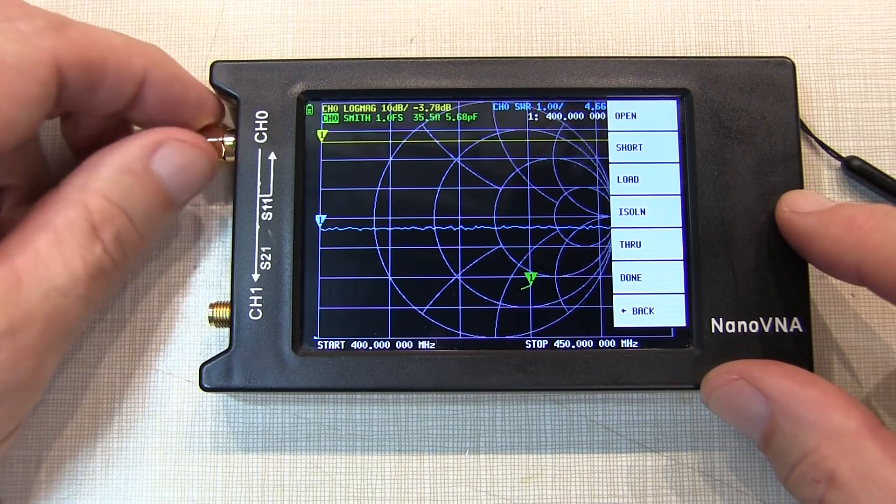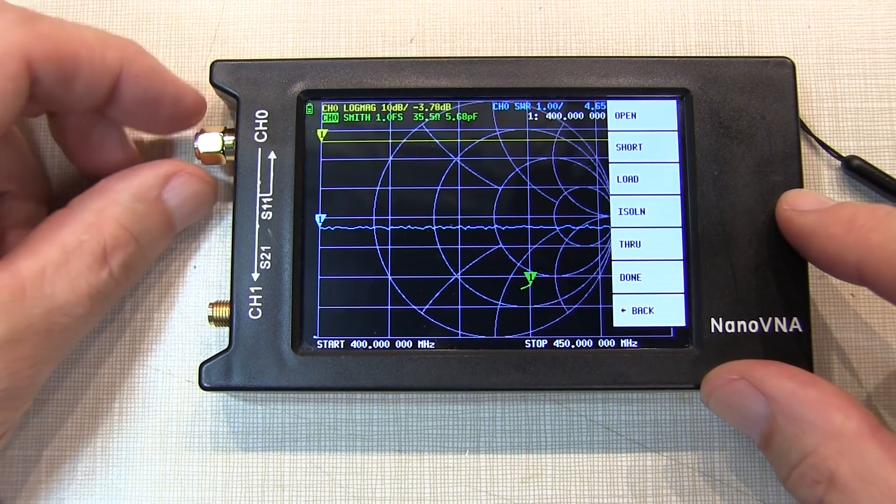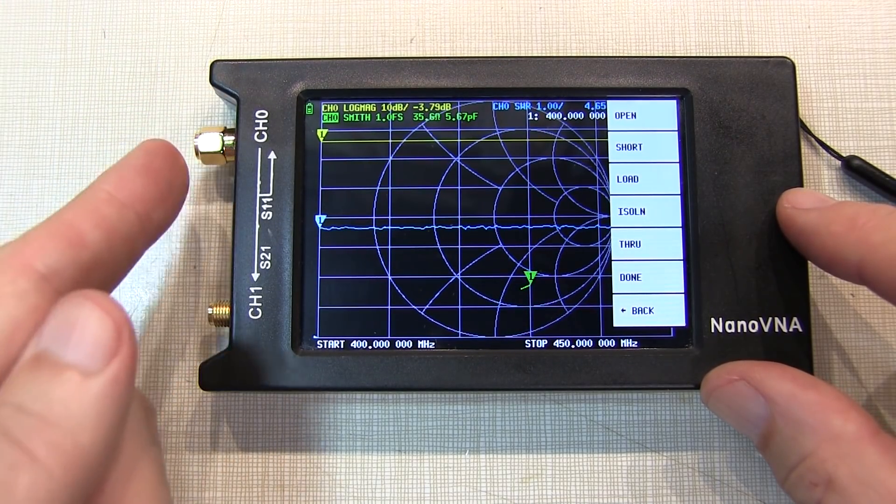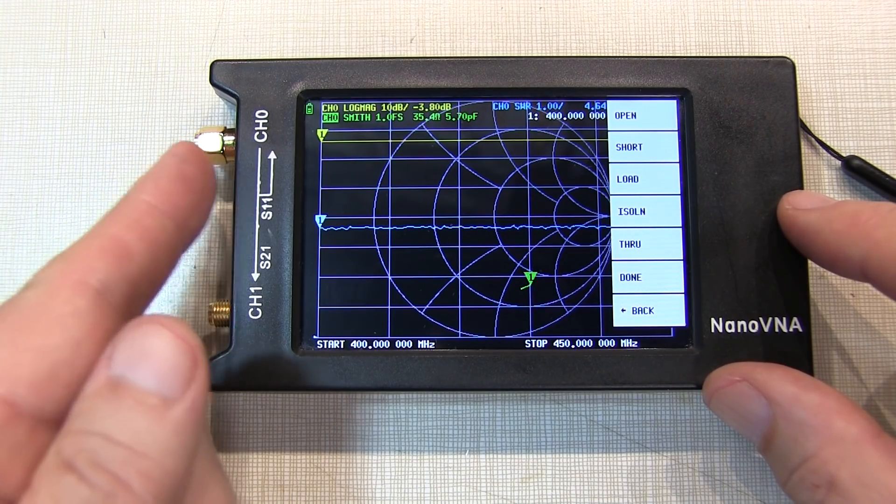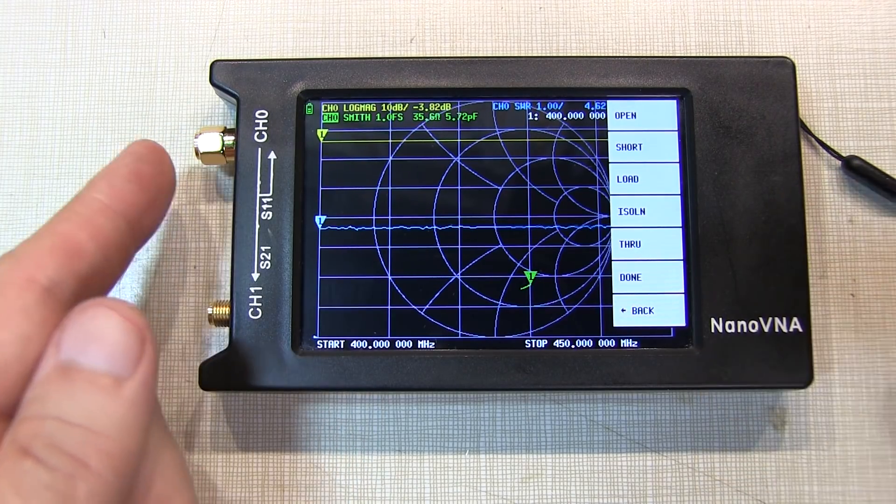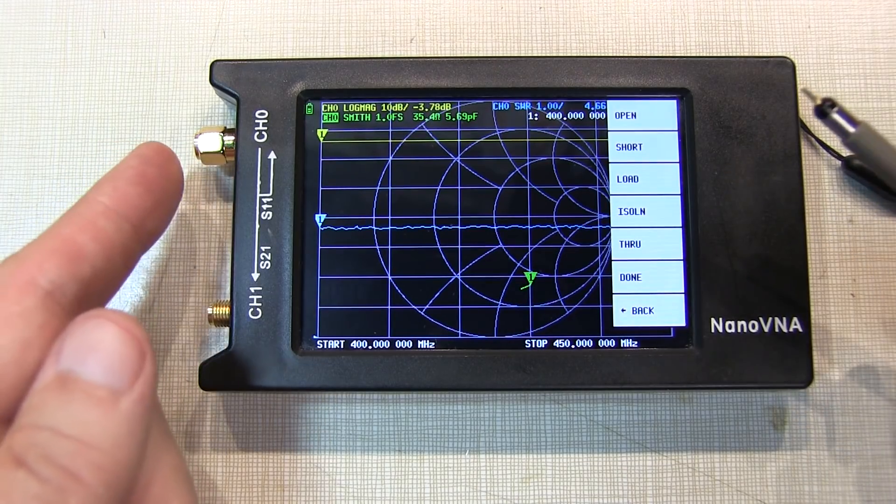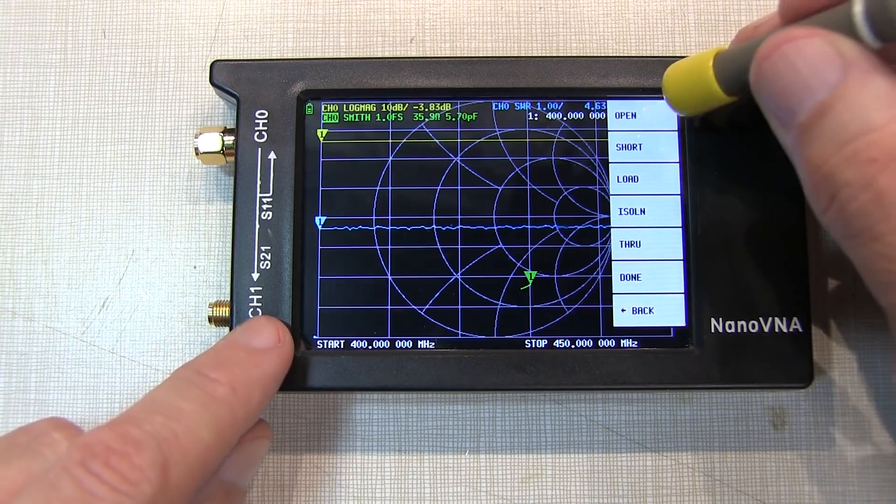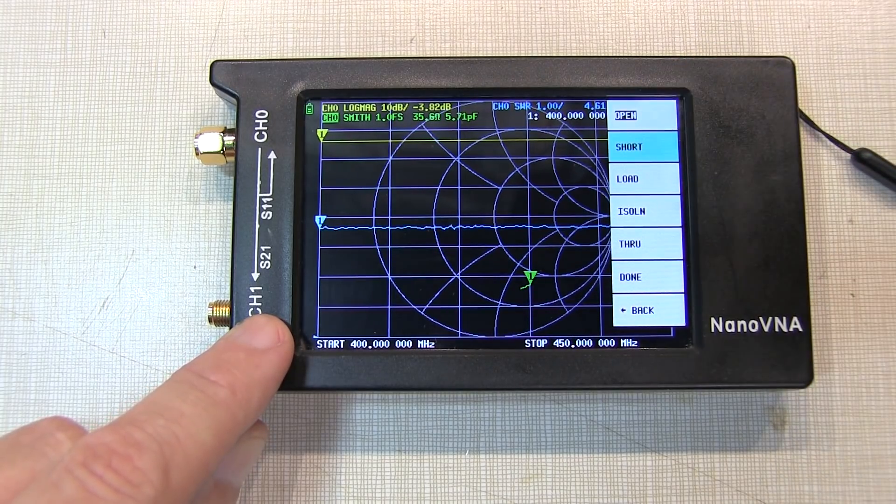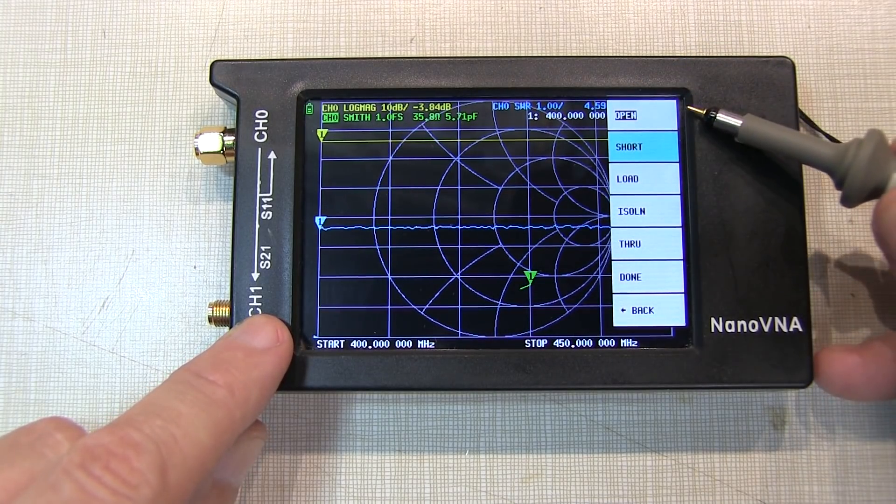We'll start by connecting the open to the port. And you might say, well, why don't you just leave the port open? Well, the reality is that you want each of these to have exactly the same reference plane, or measurement plane. So there is an open, because it kind of extends the length of the shield and things like that. At lower frequencies it doesn't matter, at higher frequencies it does matter, so it's a good practice to get into. So once I've connected the open, I just touch on open, and it makes a measurement on that. You see that's now reverse text, ready to do the short.